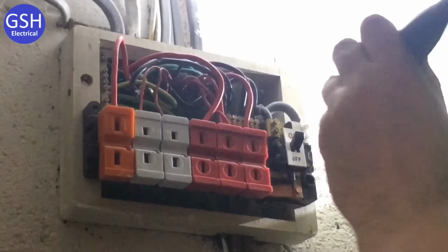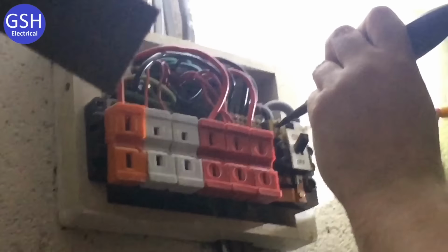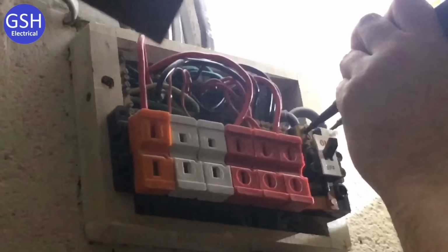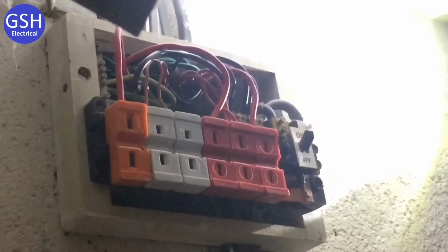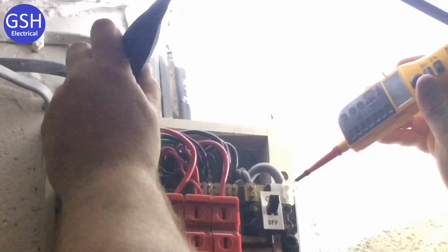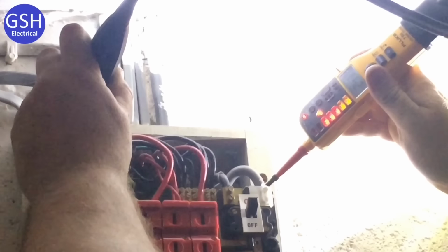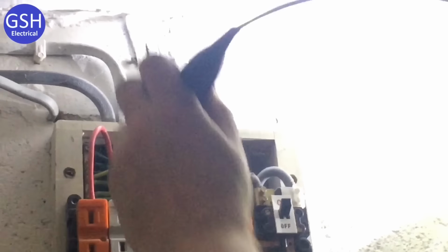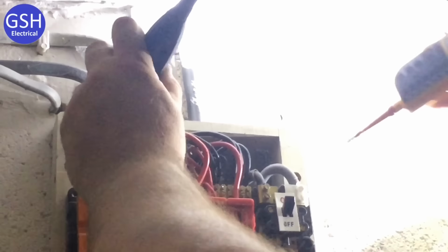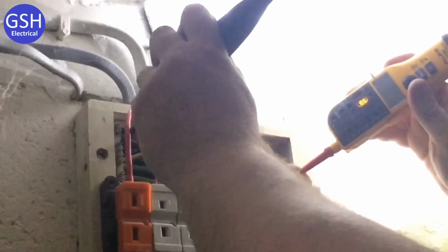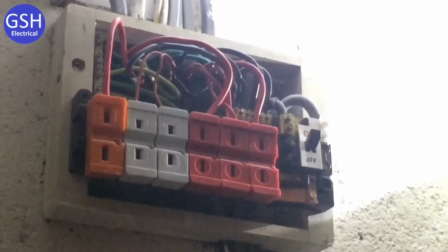So I'm going to probe onto the neutral first, and then onto line, and then off line, off neutral. Then I'm going to probe onto CPC or earth bar, onto line, and then off, and then I'm going to probe onto CPC or earth bar and neutral, and then off. So what is that confirmed? That's confirmed that the line is in the right place and the neutral is in the right place. Thank you very much. So what are you going to do now for me, Mark?